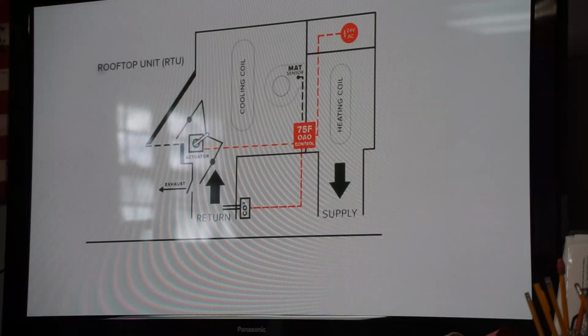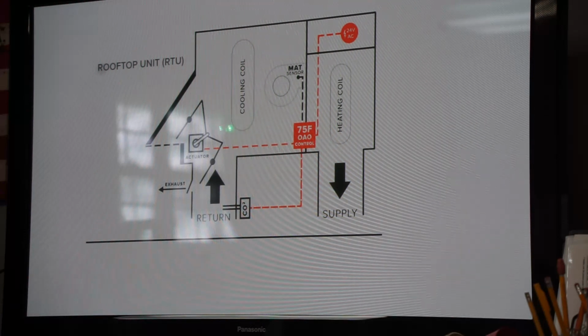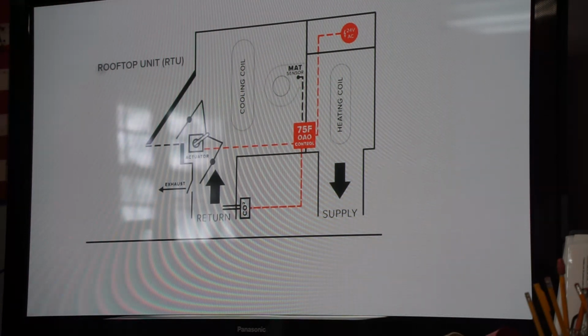So same thing, rooftop air handler. You've got one in the back. Return air, barometric relief, outside air, mixed air here, cooling coil, blower, heat exchanger, supply air. We're going to use or reference this type of drawing a lot, but this is what I want you to keep in your mind. Now, we don't typically mount that mixed air sensor at that location, but this is truly mixed air, so it's a combination of return air and outside air.